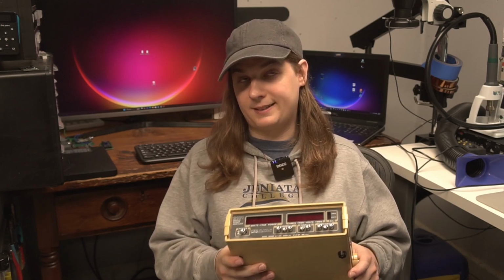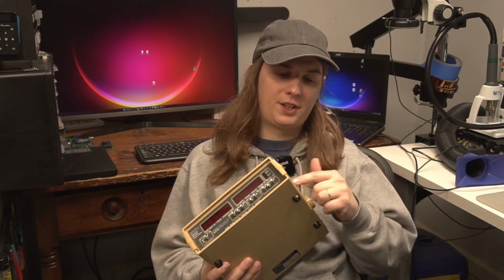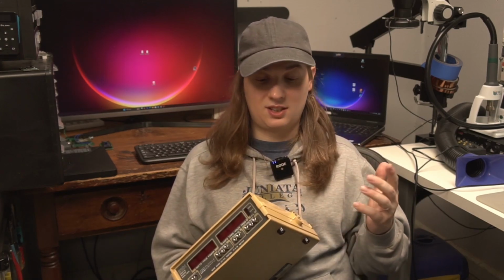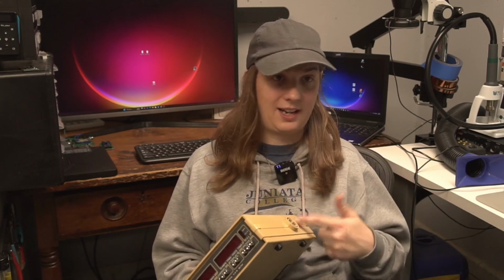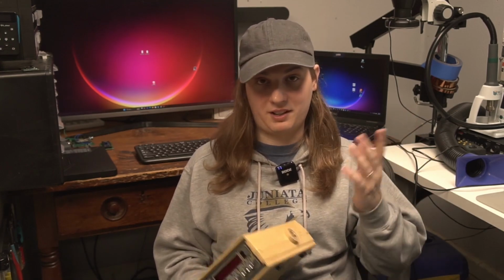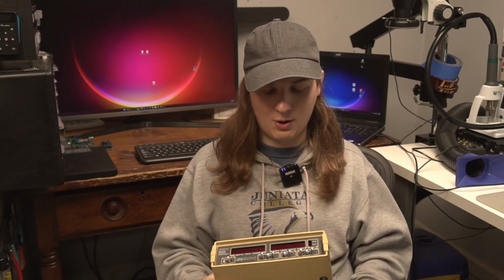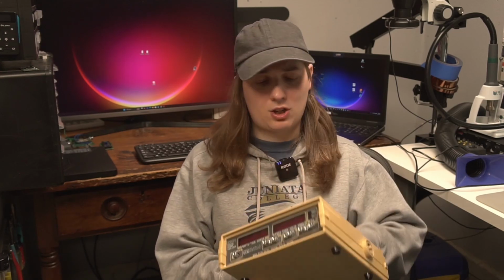We're not using NIST traceable calibration standards. We are using a relatively accurate DMM to calibrate towards. So yeah, we're going to calibrate this to the best of our ability here. We're going to follow the manual. The nice thing about these older instruments like this is they publish manuals on how to calibrate them and how to repair them, and they even have schematics available for it. So we're just going to follow the manual, go through it real quick, get this thing back in cal.